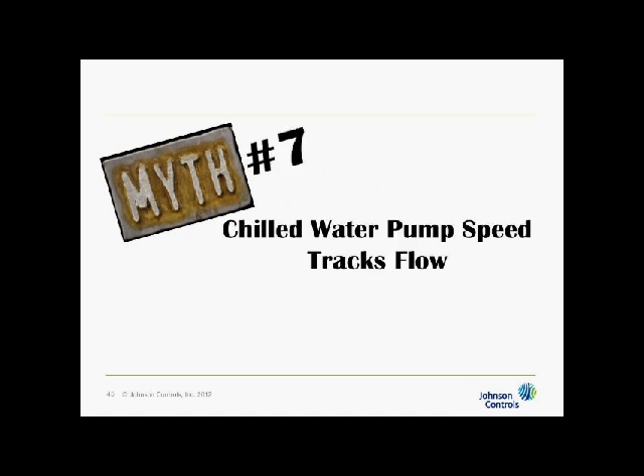Okay, so myth number 6, once again, is busted. Even with VPF systems, flow does not track load, but the negative impact of it can be reduced in the plant. Okay, myth number 7. Chilled water pump speed tracks flow. A moment ago we said flow doesn't track load. Now we have a new myth that speed tracks flow.